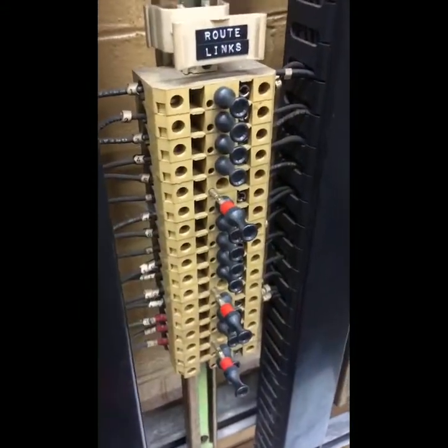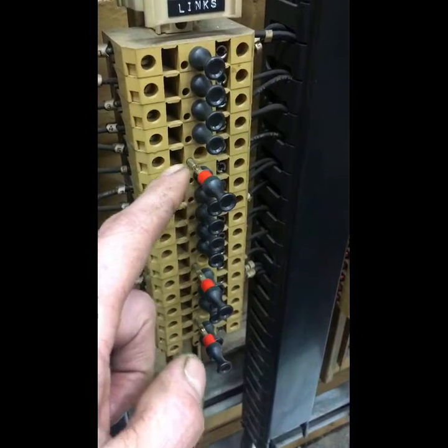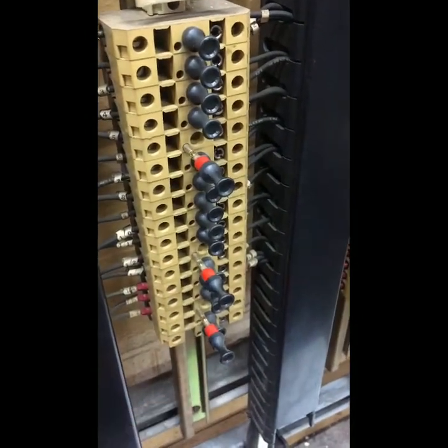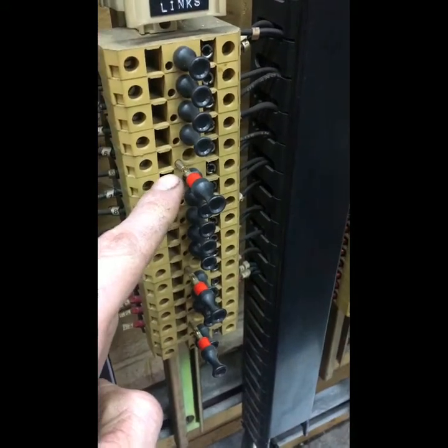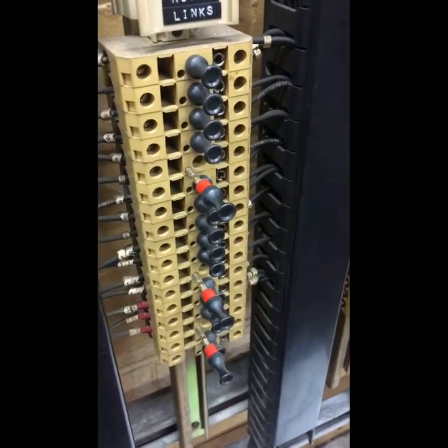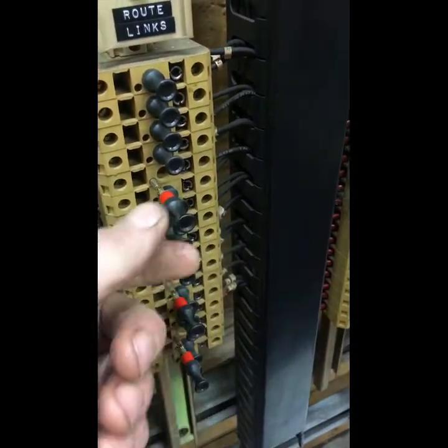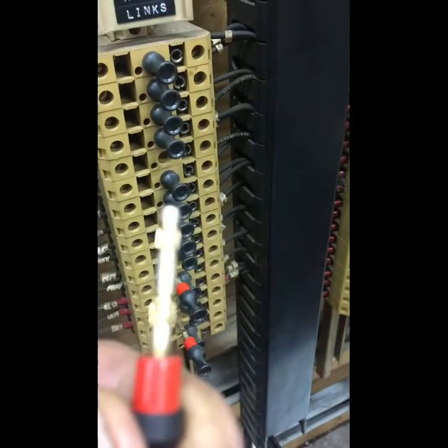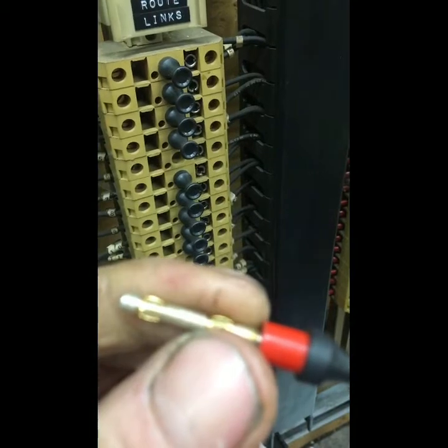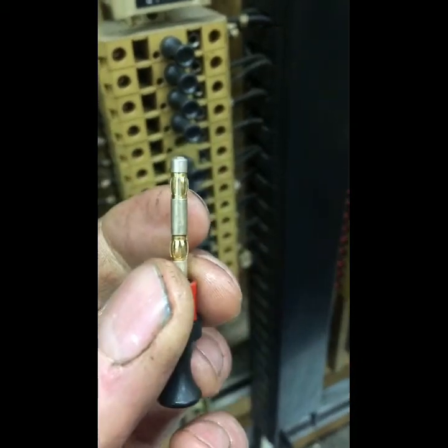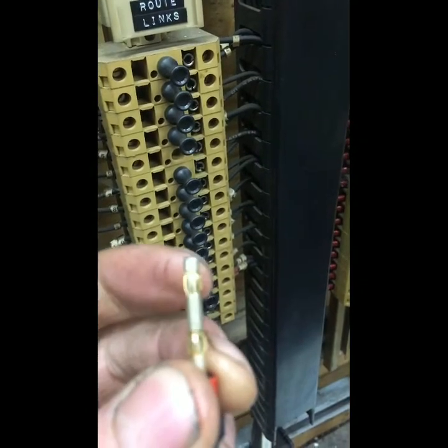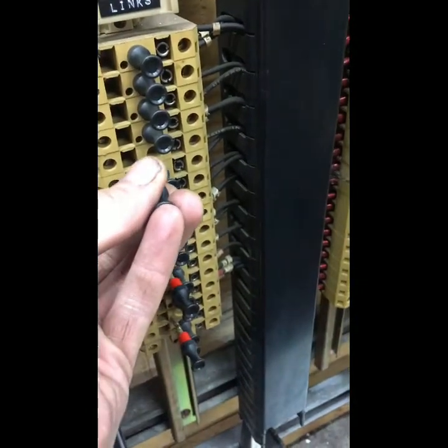Here you can see we've disconnected some of the route links, and as I mentioned, we've put them into the standing peg holes on the side so we can see that they are there. And also you'll notice the little red line that is now apparent, so you can visually see, hello, something disconnected here. There you go. And all they are is little push pins. Over time it has been known for these to go high resistance. These are in a very good state actually, considering they've been in for about 20 odd years. They have little expanding touch points there that make the circuit inside.